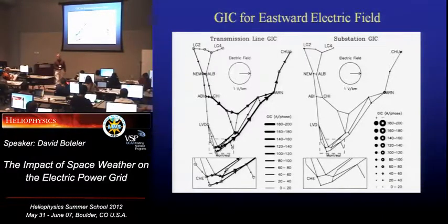How sensitive is this to your underlying model of what the conductivity is, what your conductance profile within the Earth? In the Earth, yeah. Right, the question was, how sensitive is this to the Earth conductivity structure? And yes, it is quite sensitive to that. That's one of the contributing factors for Hydro-Quebec, because it's on a very resistive Earth layer there, so you're getting larger electric fields as a result. That's one of the factors that has to be taken into account.